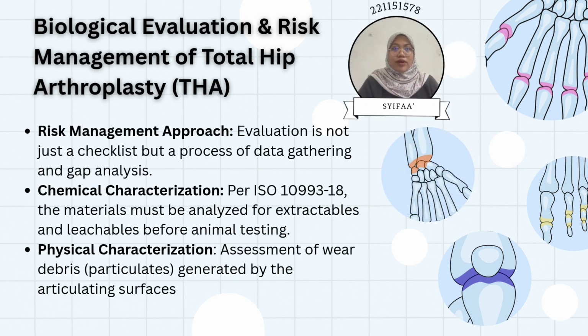ISO 10993-1 has shifted from a simple test list to a risk management process. It is about being smart with data before we ever enter a lab. We start with chemical characterization. We analyze extractables and leachables, essentially checking what chemicals might leak out of the metals or plastics. By identifying this early, we can predict toxicity risk without unnecessary animal testing.